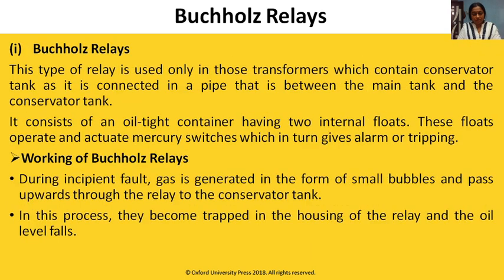Now first we'll see Buchholz relay. This type of relay is used only in those transformers which contain a conservator tank, as it is connected in the pipe between the main tank and the conservator tank. The Buchholz relay is connected between the transformer tank and a conservator. The conservator is fitted above the transformer tank. The Buchholz relay is connected in between that conservator tank and the main transformer tank.